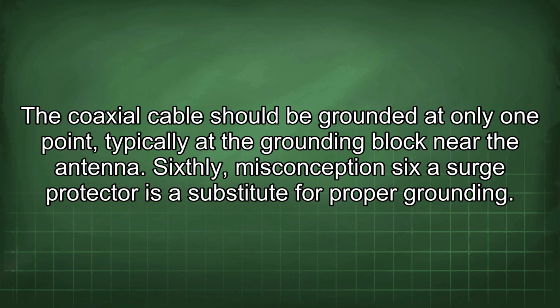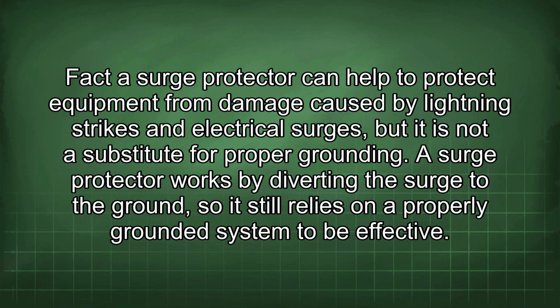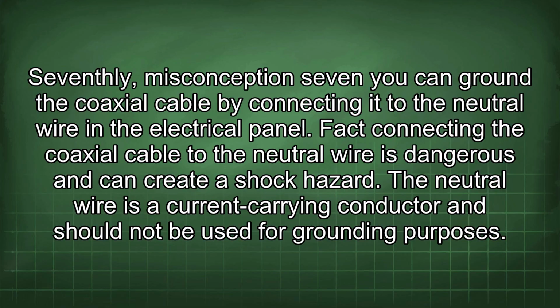Sixthly, misconception 6: a surge protector is a substitute for proper grounding. Fact: a surge protector can help to protect equipment from damage caused by lightning strikes and electrical surges, but it is not a substitute for proper grounding. A surge protector works by diverting the surge to the ground, so it still relies on a properly grounded system to be effective.